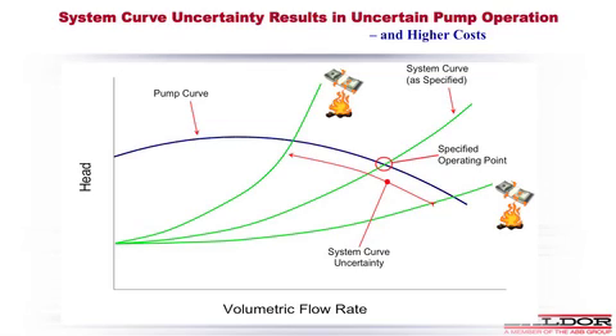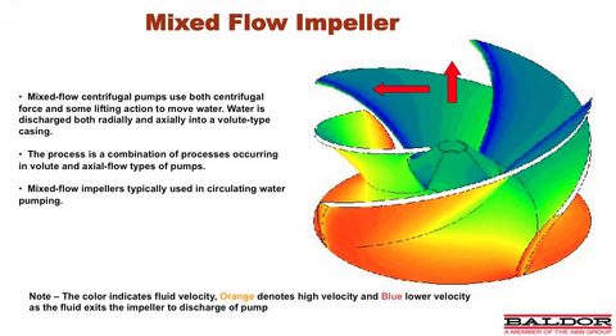The screenshot you're looking at is showing a system curve with 3 load points laid over the pump curve. You can see where the red circle is, we're showing the specified operating point. And the 2 points where the flames are burning the dollars, we're showing you on the left of your screen where the pump is getting pushed back on the curve in the case of high condenser back pressure. The pump is being forced back on the curve. At the right, that's where the pump is running to the right of the curve and away from its best efficiency point. In both cases, this results in reduced efficiency, higher operating cost, and reduced reliability. The typical circulating water pump utilizes what they call a mixed flow impeller.